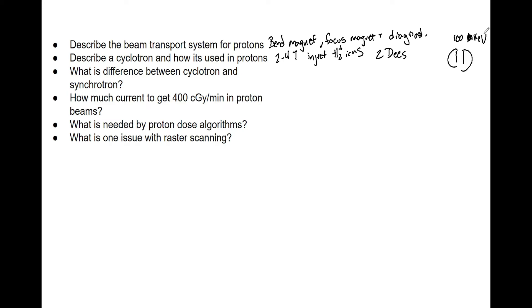The protons are extracted from the accelerated H2 ions by hitting a stripping foil which is made of graphite. That term is called stripping. You're just using the graphite and those ions hitting that foil is going to strip and allow you to take the protons. That removes the electrons from the ion beam.